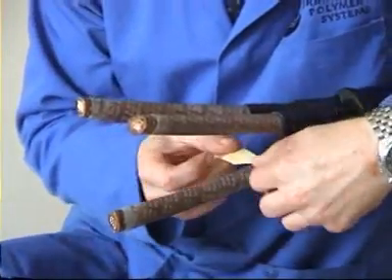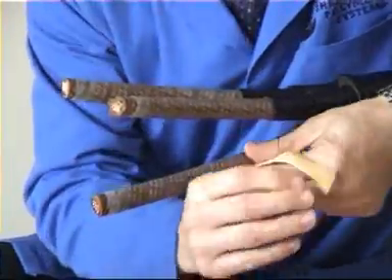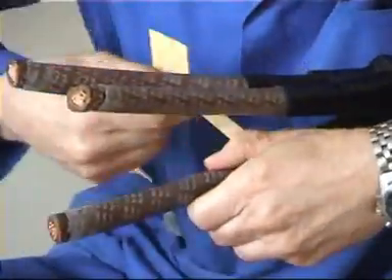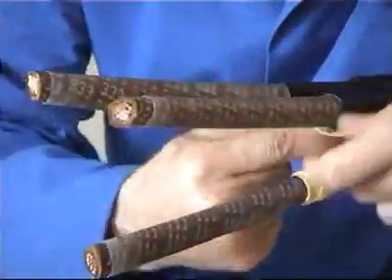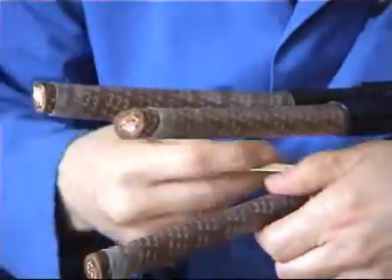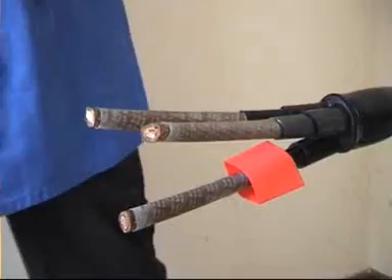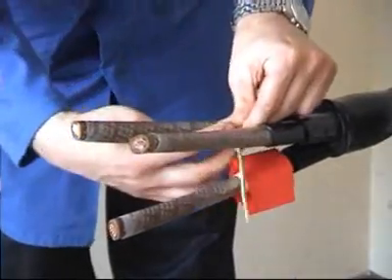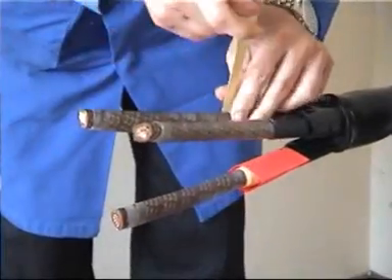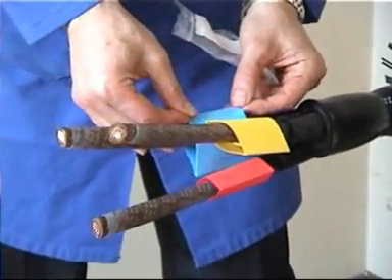Because we've now created new stress points at the end of the conductive tubes, we now apply yellow stress tape to the end of each tube, overlapping 10mm either way. Just as we did on the XLP cable, we fit the coloured shrink sleeves over the stress tape as before.